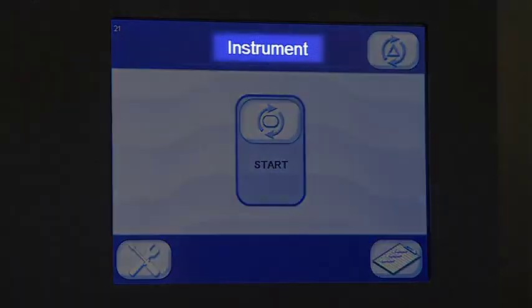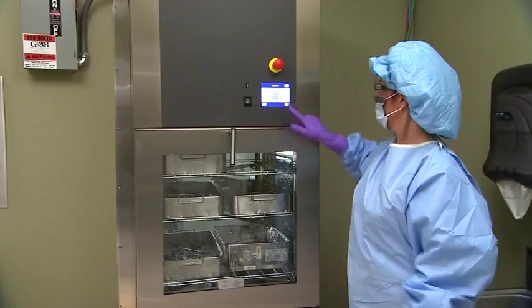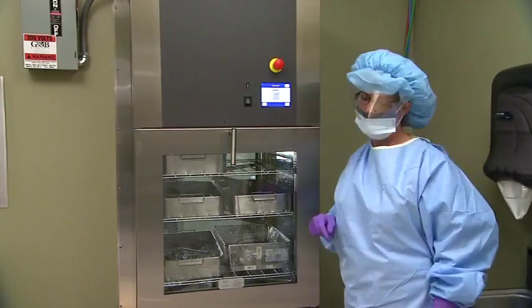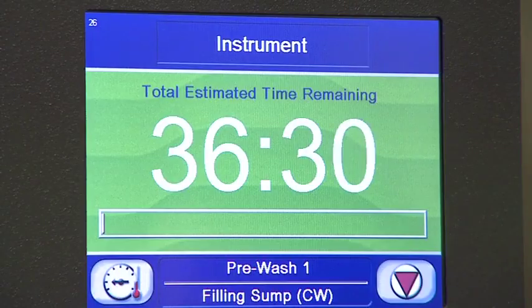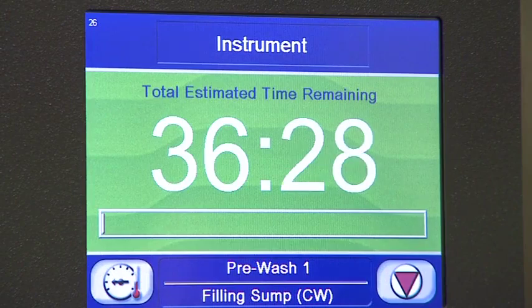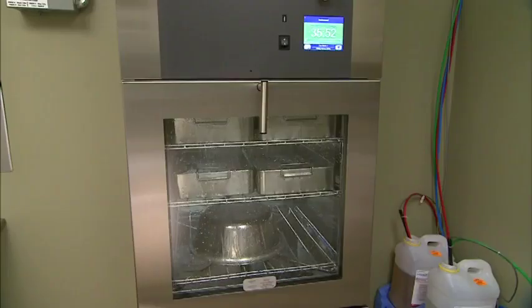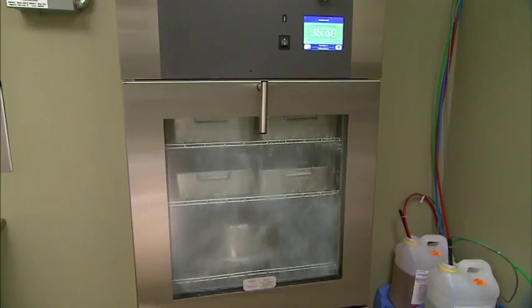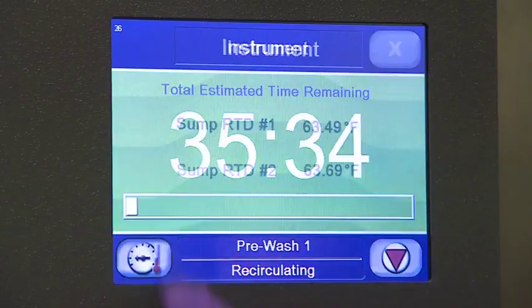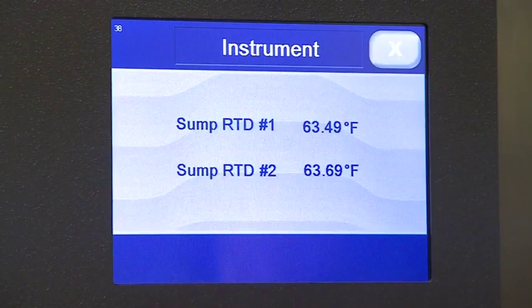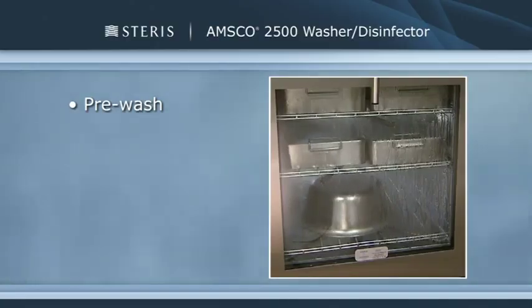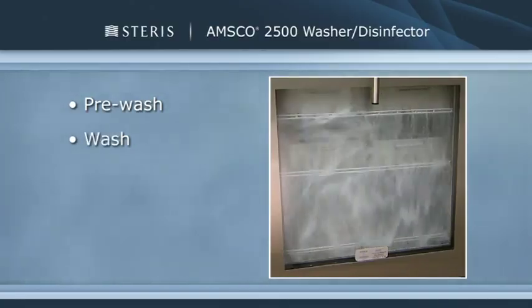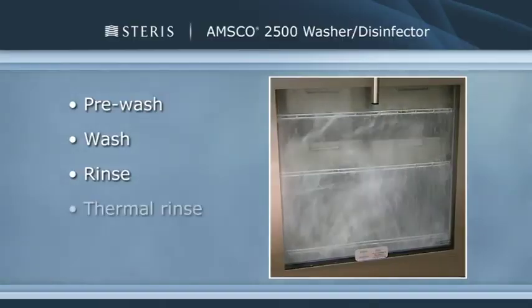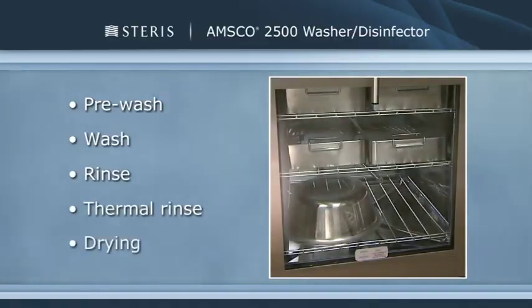Confirm the appropriate cycle is displayed on the Ready screen, or press Select Cycle to choose a different option, then press Start. In a typical cycle, the cycle in process screen is displayed throughout and shows the estimated time remaining to cycle completion. As the cycle progresses, an operator can press the Details button to view current cycle data parameters. Cycles include a pre-wash phase, a wash phase, a rinse phase, a thermal rinse phase, and a drying phase.